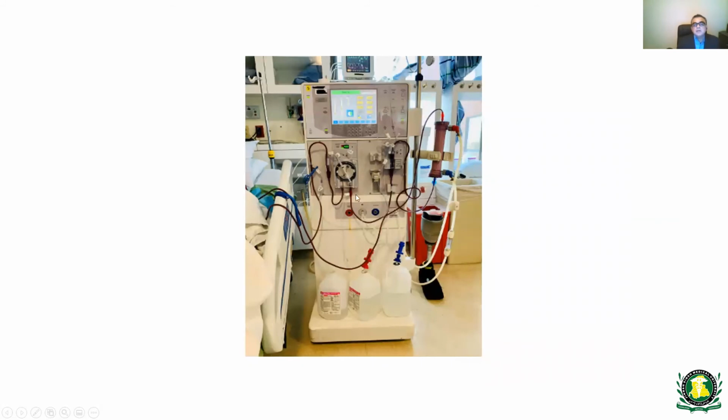So this is the dialysis machine. You see that this line is the arterial line. It goes through the tubings into the pump, which pushes the blood towards the dialyzer. It's going up, and this is the red port. So that's where the blood is going. Blood is going from top to bottom, and then you see these two connectors here. This is the special dialysate fluid, which has bicarb and acetate mixed to have an optimum pH.